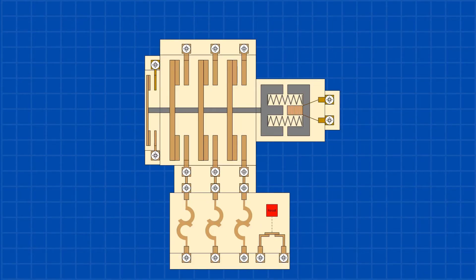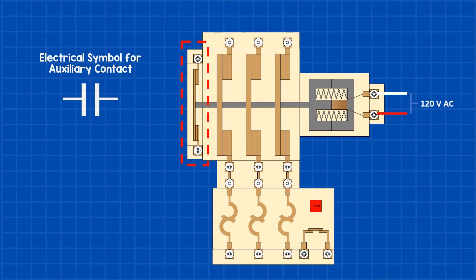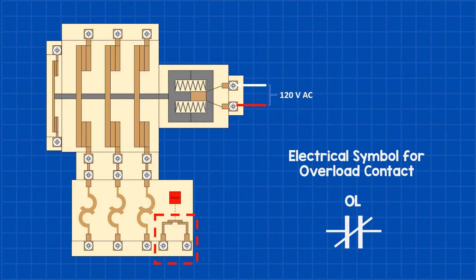Before we get into the 120 volt AC control side, we need to talk about two other components on the starter: the auxiliary contact and the overload contact. These will play a key role in the start-stop control circuit. The auxiliary contact is connected to the main contactor and closes at the same time. It's mainly used in the control circuit to show when the contactor is activated. It also helps latch the circuit, but I'll explain that in more detail when we get to the control circuit. An overload contact is a normally closed contact that opens when an overload occurs and needs to be manually reset using a reset button. In the control circuit, it disconnects the circuit when an overload is detected.